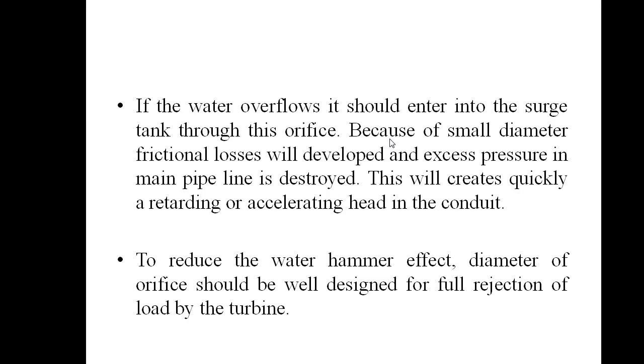Because of the small diameter, friction loss is developed and excess pressure in the main pipeline is destroyed, and this will quickly create a retarding or accelerating head in the conduit, and reduce the water hammer effect, which we have already discussed. The diameter of the orifice should be well designed for the full rejection of load by the turbine.